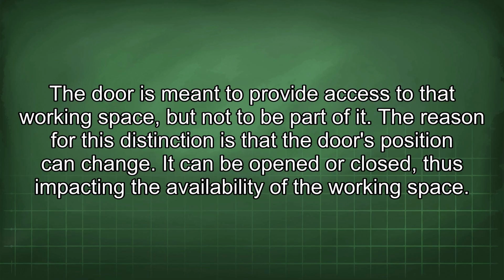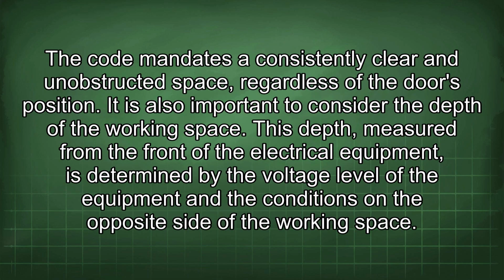The reason for this distinction is that the door's position can change. It can be opened or closed, thus impacting the availability of the working space. The code mandates a consistently clear and unobstructed space, regardless of the door's position. It is also important to consider the depth of the working space. This depth, measured from the front of the electrical equipment, is determined by the voltage level of the equipment and the conditions on the opposite side of the working space.